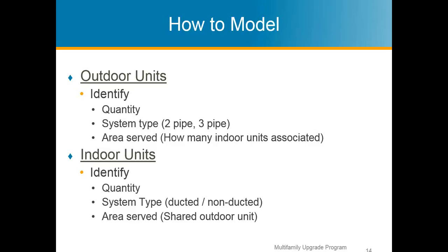So indoor units, they come in many different types. Ducted, non-ducted, you can have them concealed. You have these cassette units, is what they call them. Typically, for apartment units, you're just going to have one for each apartment unit. And if you're single family or office spaces, you can have one condensing unit serving multiple indoor units. So like your living room might have one, your bedrooms may have an indoor unit, and if nobody's in the bedroom and it's not calling for any heating or cooling, then it gets to throttle that outdoor unit down, and you find a lot of those savings through the variable speed drives and the compressors and the staging and stuff like that.